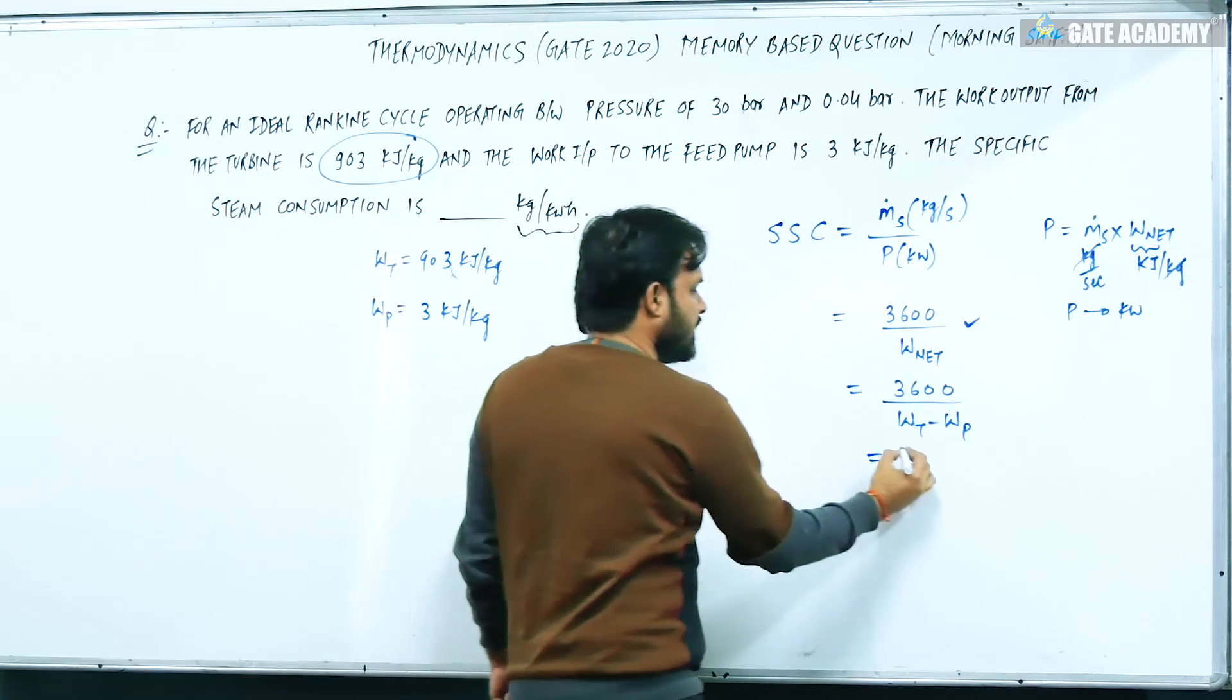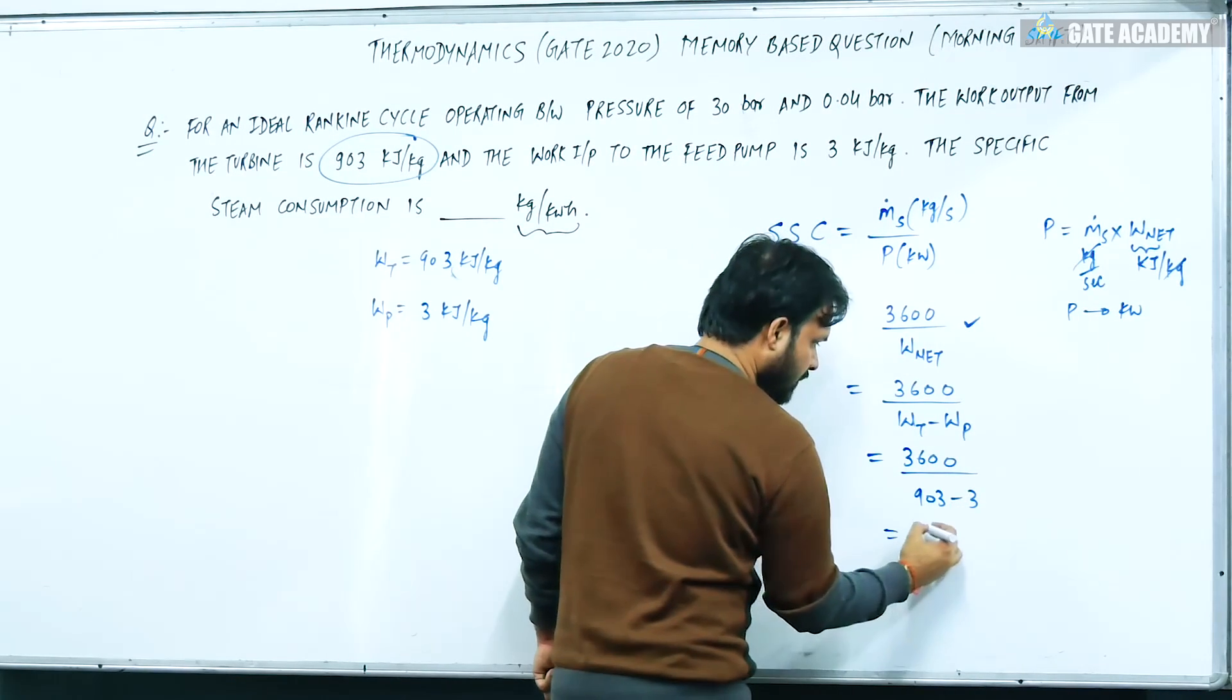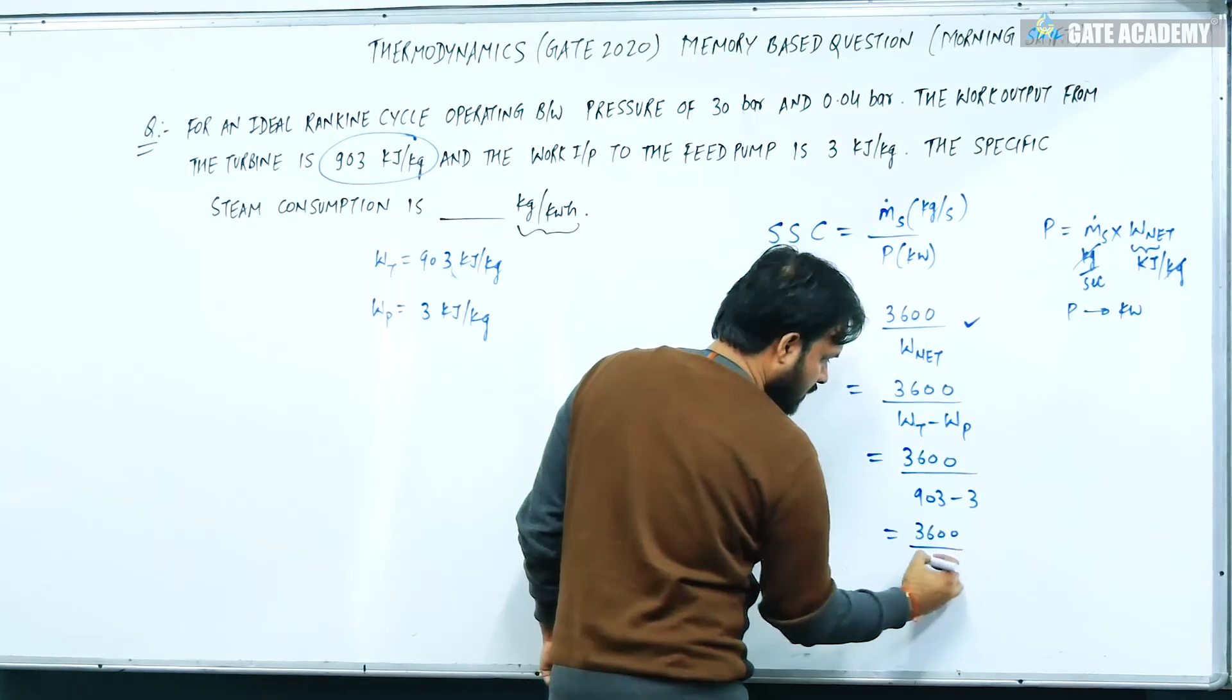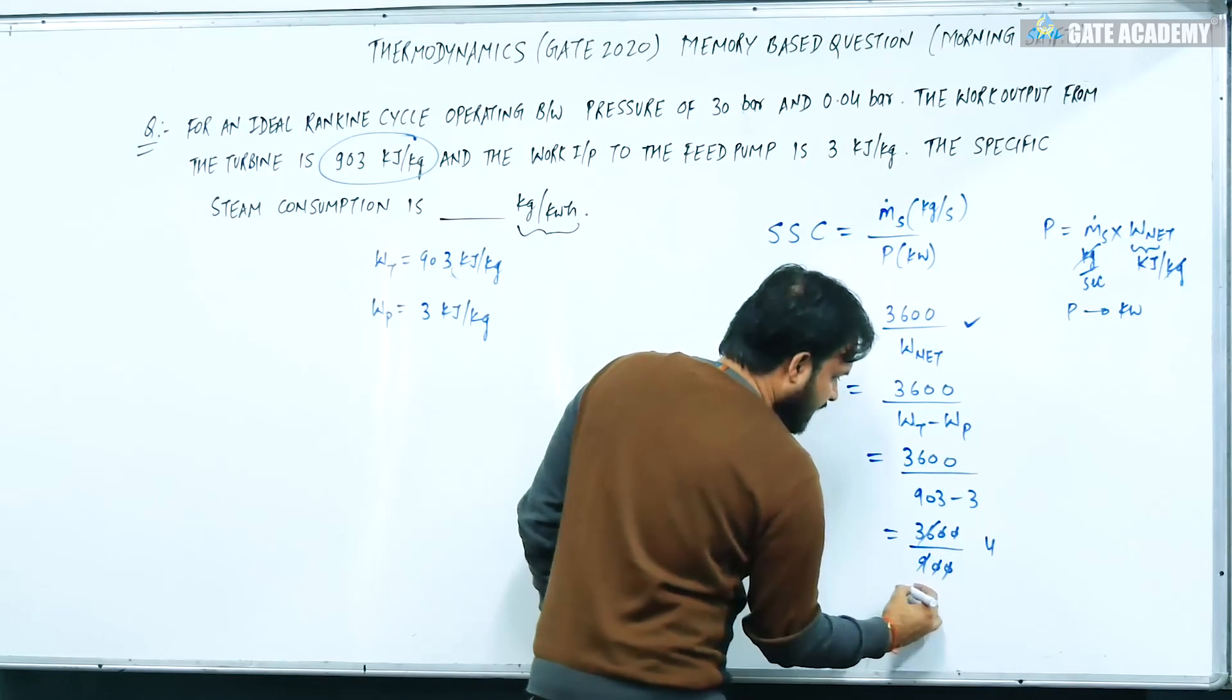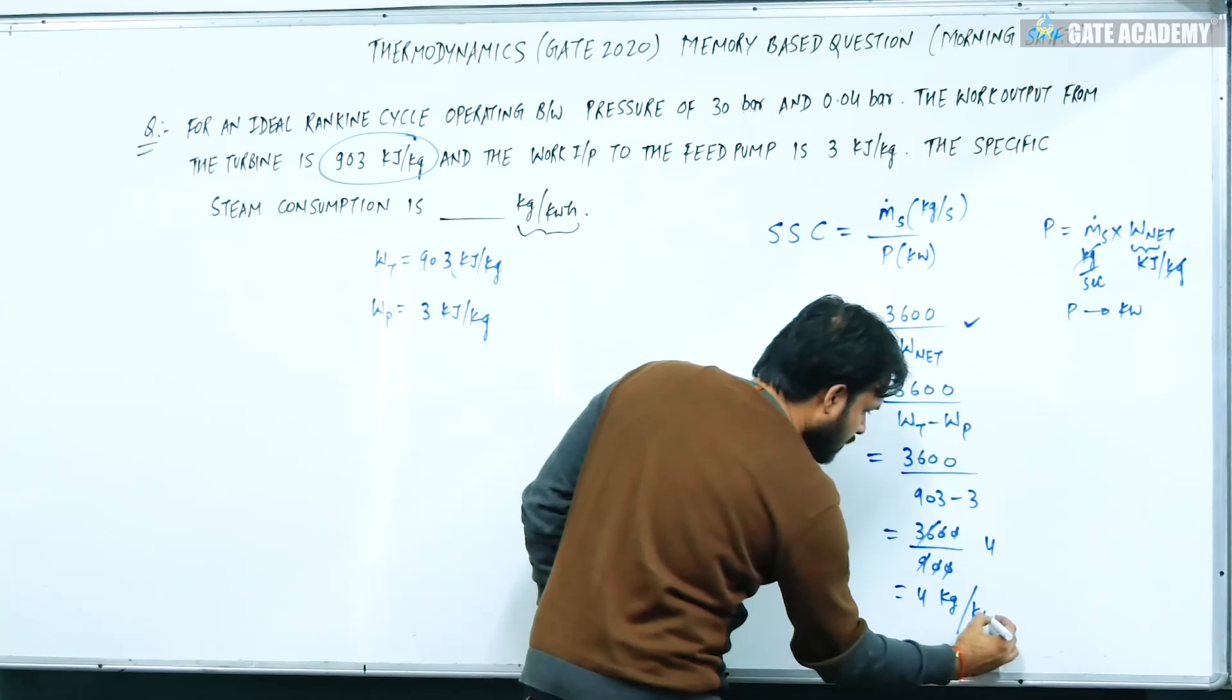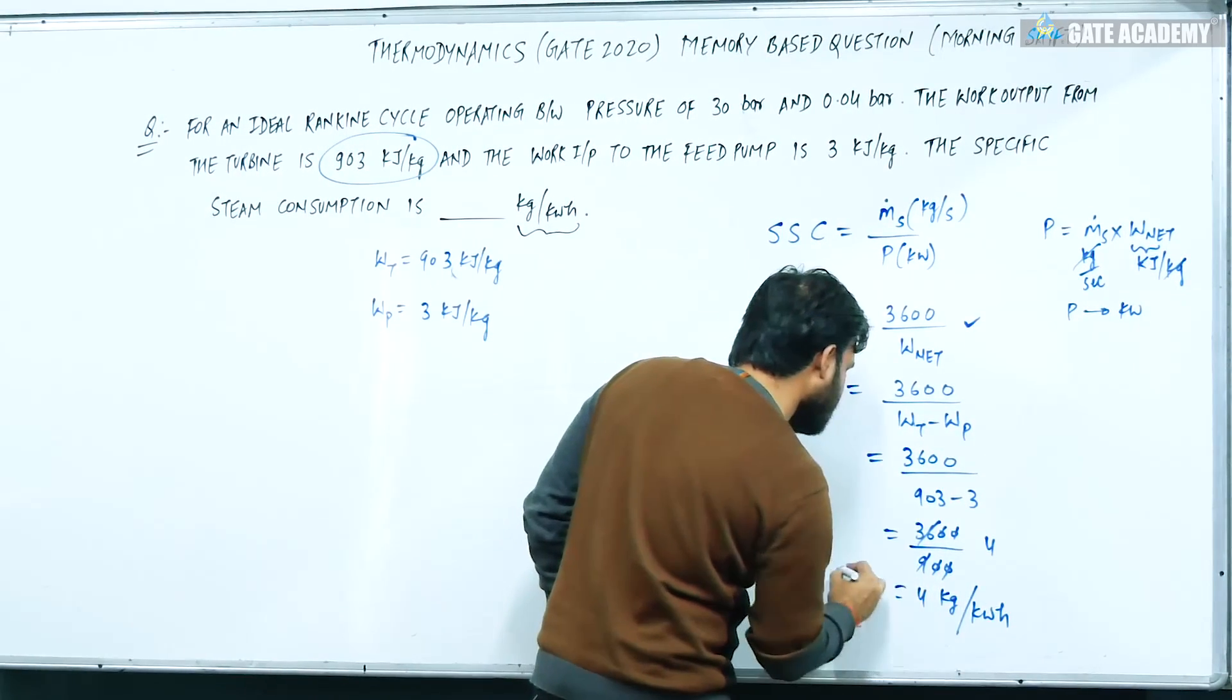So what will you find? 3600 upon 903 minus 3. This will be 3600 upon 900, and this will be 4 kilogram per kilowatt hour, which will be the specific steam consumption.